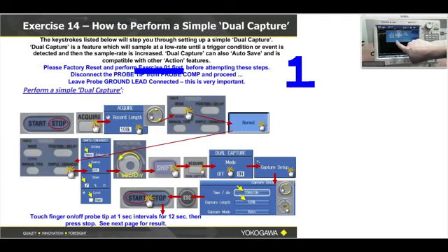That would save it to file, which is very powerful, actually. But if you don't have a USB thumb drive or other media installed, it'll give you an error message. So there's no check mark on action. Once we feel good about these settings, press the escape button just one time, and then go over to start stop and press start.